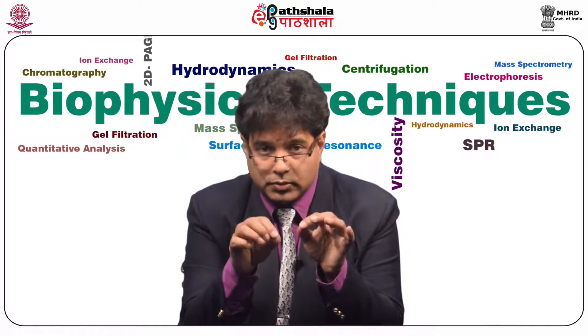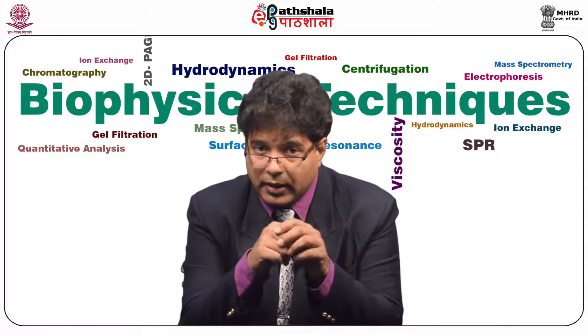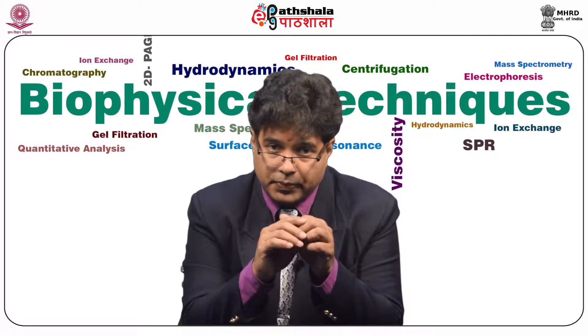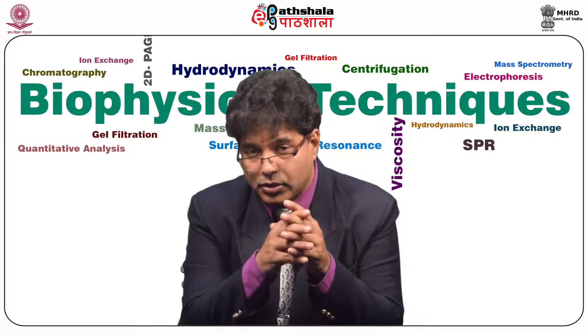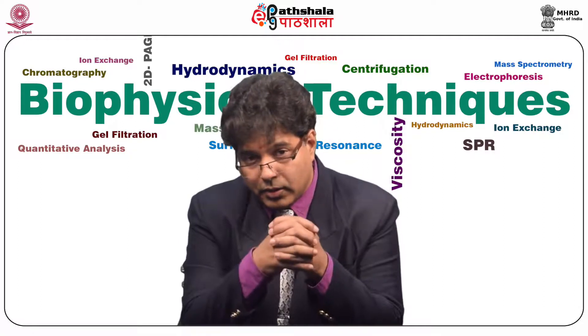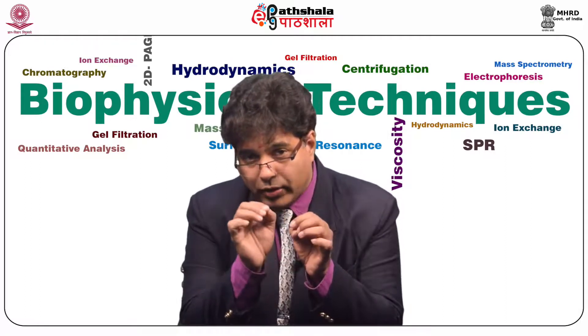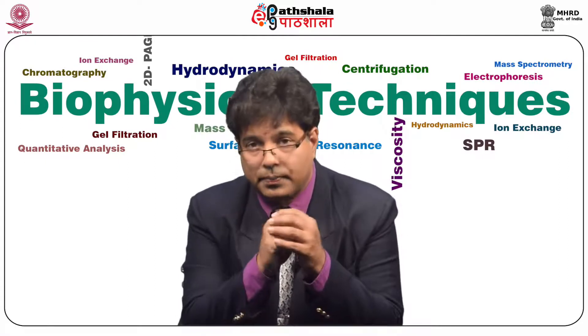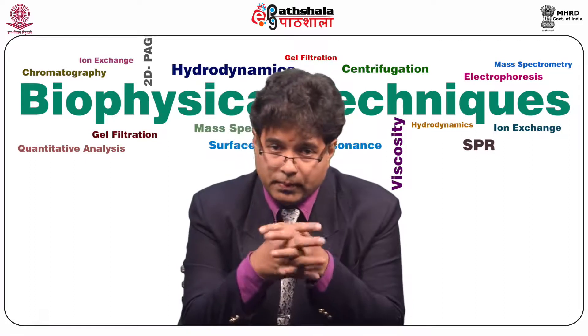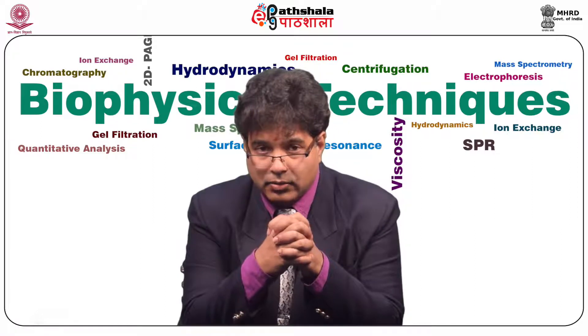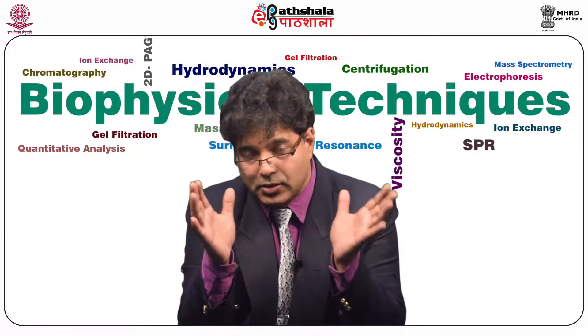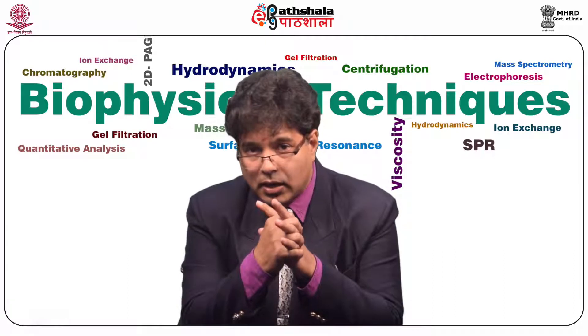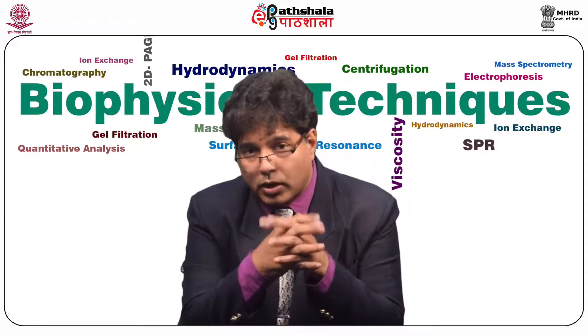In quadrupole mass spectrometry, acceleration is done using RF (radio frequency) voltage and a DC voltage, alternated to resonate a particular mass so it can be isolated, accelerated, and propelled towards the detector. Time of flight uses a reflectron to increase the path of ions, giving better resolution. Magnetic field deflection and time of flight give a somewhat different picture compared to quadrupole mass spectrometry.